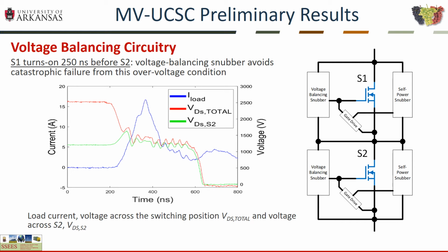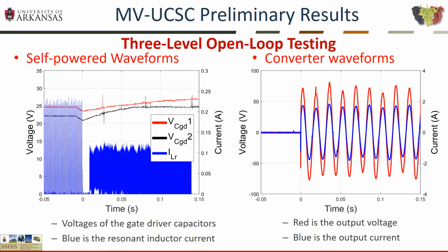Here are some examples showing the operation of the voltage balancing circuitry. We selected that S1 turns on 250 nanoseconds before S2, so the voltage across S2 should rise to the DC bus, and in this particular case should cause destruction of this device because we are applying 2.4 kilovolts. Here in red you have the DC bus. This is the load current, and you can see that the voltage across the switch S2 remains within its safe operating area. And then finally, both devices S1 and S2 turn on. So the balancing circuitry works well.